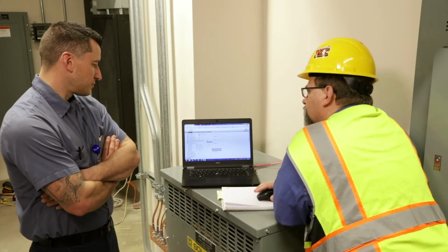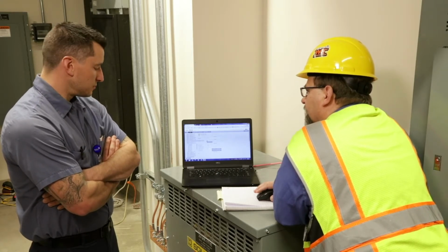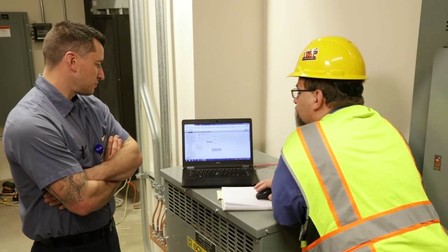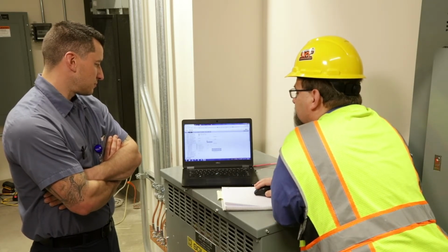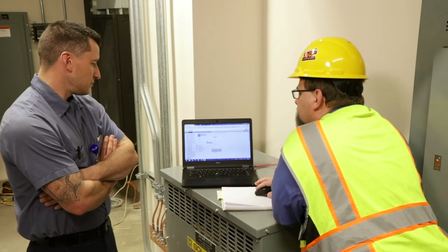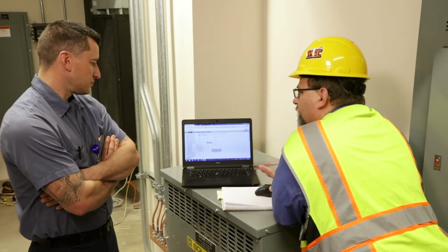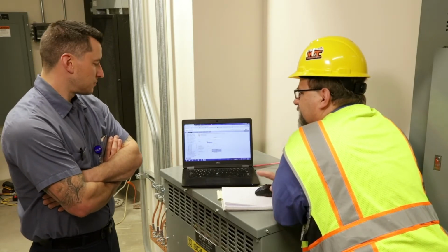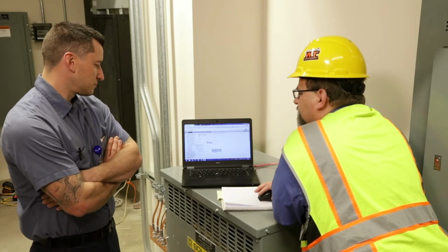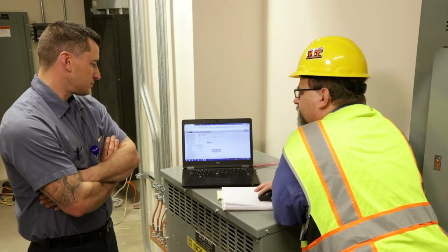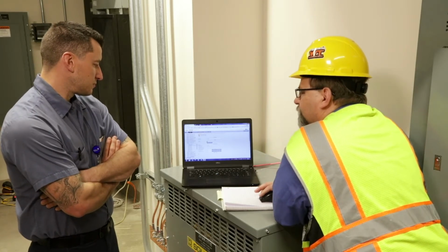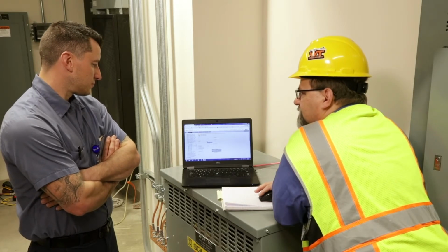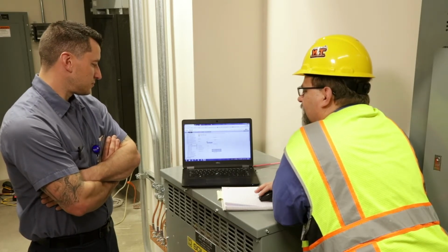All right, it helps you troubleshoot too, so you can see if things are online with the network and change the status of loads. And don't worry, because you can come in here and change the name of this load. I can click into this text area, and instead of load A, I can call it the under counter light for nurse's station. You're limited to like 21 characters, so it gets tedious if you label the room that way. But you should be able to find on the drawings a room 3H11, and it should be some kind of hallway, and the drawing will show the lights and the loads, and you'll be able to figure out which one's which.